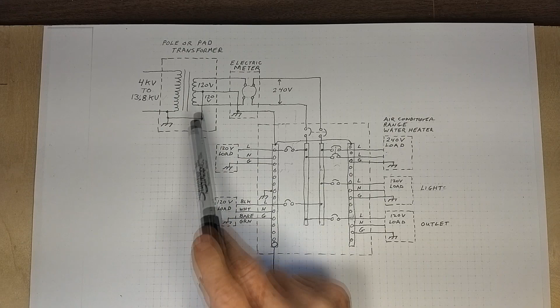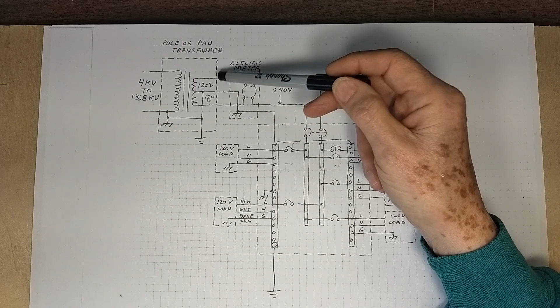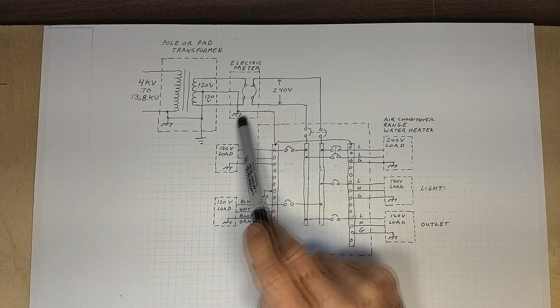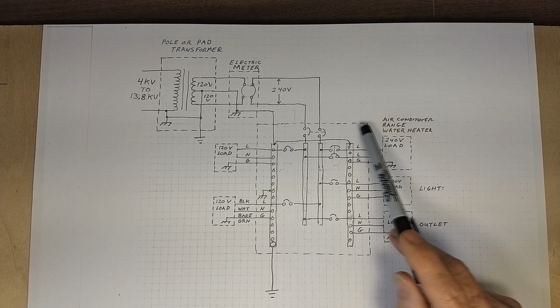And of course, the case of the transformer is also connected to the ground. This is sometimes called the 3-wire Edison system, where you have 240 volt center tapped. And that'll run to your electric meter. And of course, that'll be running back to ground, the enclosure of the meter. And then the 240 volts in the center tap will run to your load center.